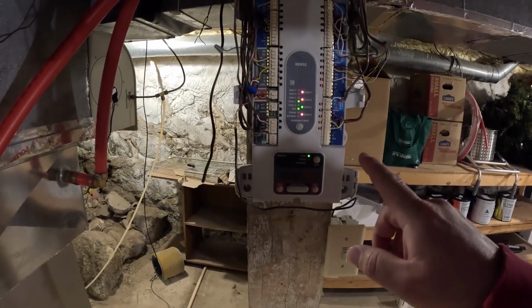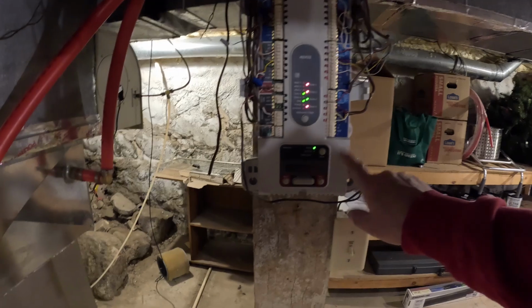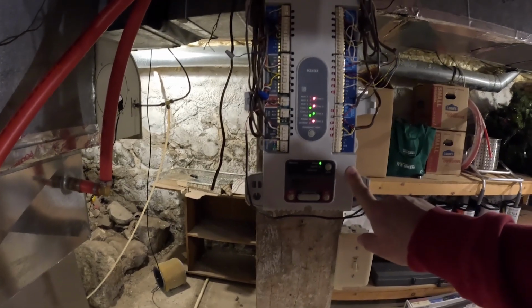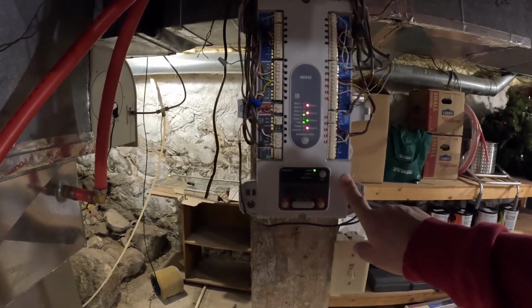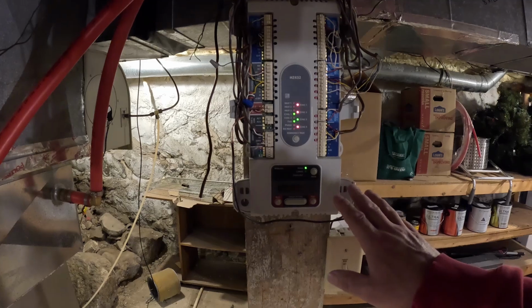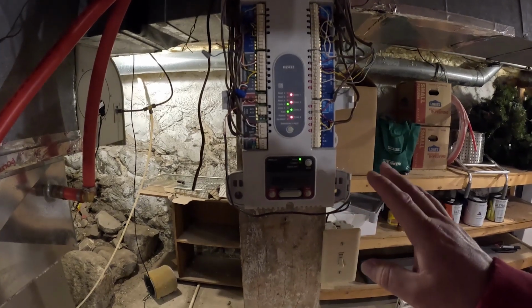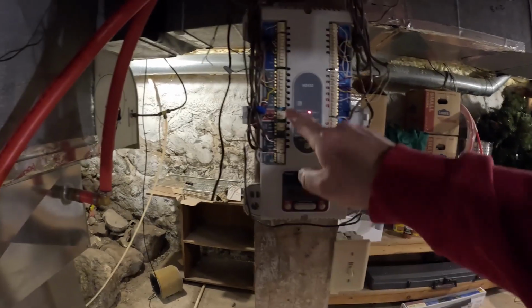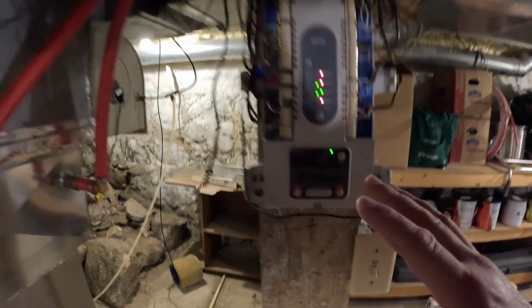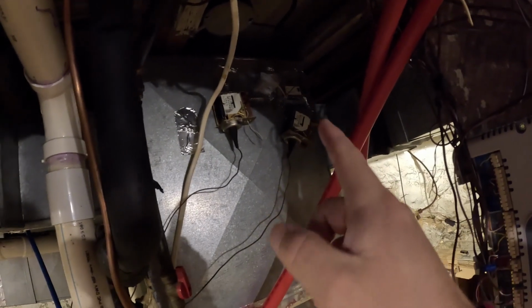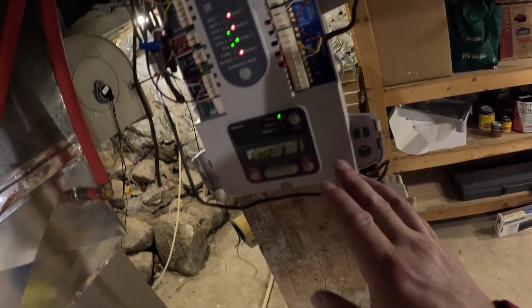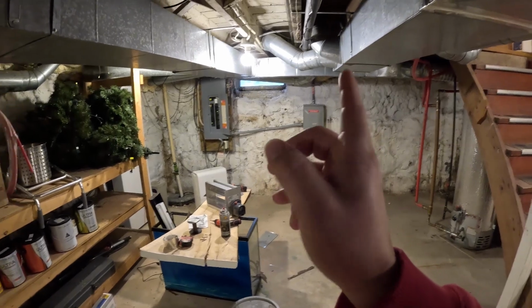This is my zoning panel, the biggest one Honeywell makes, the HZ432. It has 4 zones and can control a lot of dampers, plus add-a-zone and everything else. I also added the DATS discharge air temperature sensor, which it didn't have, and I ran an outdoor air temperature sensor too.